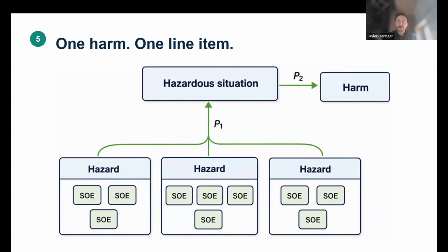Now, one of the things required to prove a risk control reduces risk is we need objective evidence, or verification of effectiveness. And this control is extremely hard to prove effective, because once the device is in the field, we're not exactly sure how the patient will interact with it. Once they see the LED blinking, they have to go look at the IFU: what does this LED mean, what does that troubleshooting mean, is this something I have to take off right away? And then they're diving in. Is every single patient going to do that?